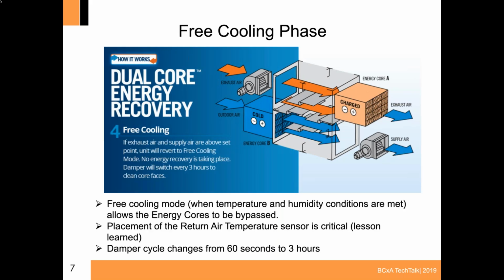There is also a free cooling phase, when the temperature and humidity conditions are sufficient that you can bring in 100% outdoor air without any pre-treatment. The cycle changes from 60 seconds to 3 hours, and then it would flip again just to stop any dirt or debris that might build up on the outside of the energy cores. The placement of your temperature sensors, and we will talk about this a little bit later on, is really, really important because it can help not mislead you into making some incorrect assumptions.